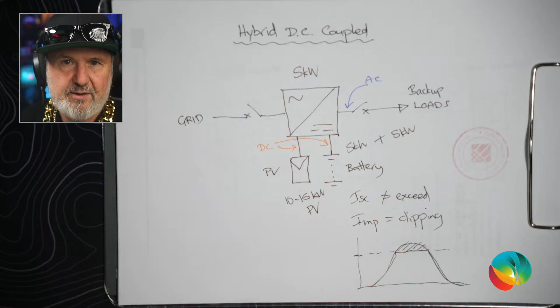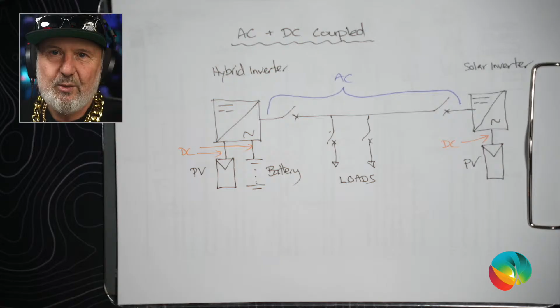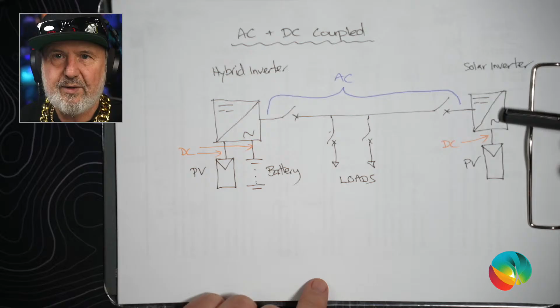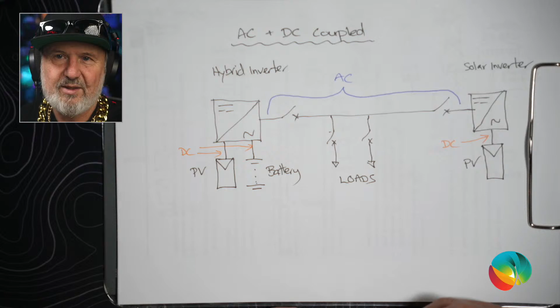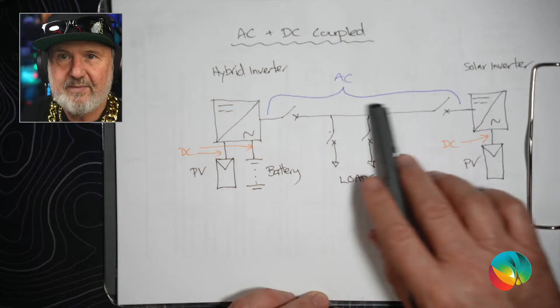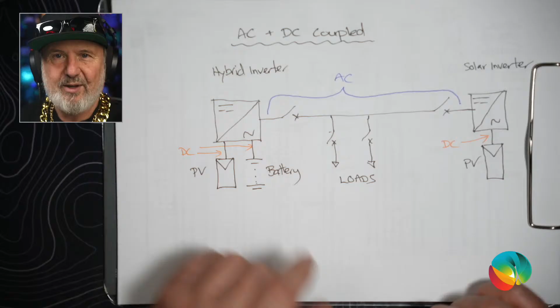All right, let's look at the next diagram. Now you might think you have to make a choice: do I have an AC coupled system or a DC coupled system? Well actually, you can have both. Here's an example: I've got a hybrid inverter with solar and battery connected, so it has DC coupling internally. And I've got a solar inverter on my switchboard connected to the same loads as the hybrid inverter. That coupling is AC. Now a word of caution: not all hybrid inverters are bidirectional.